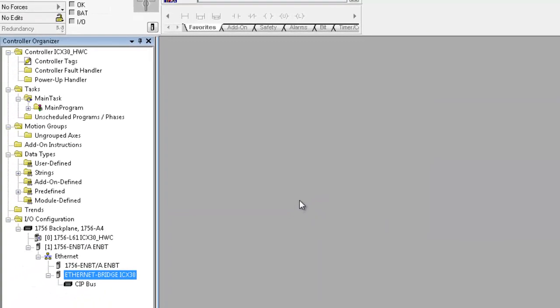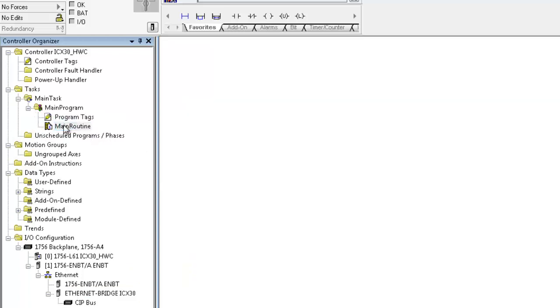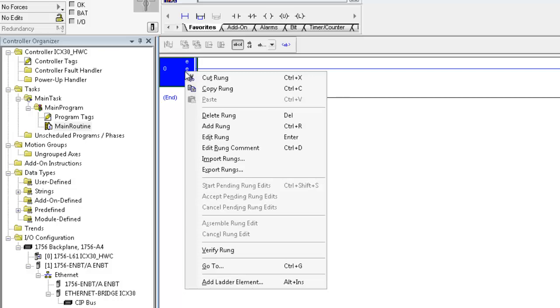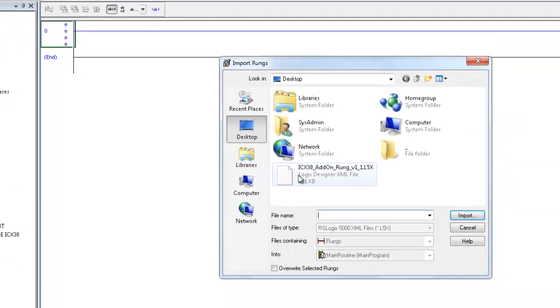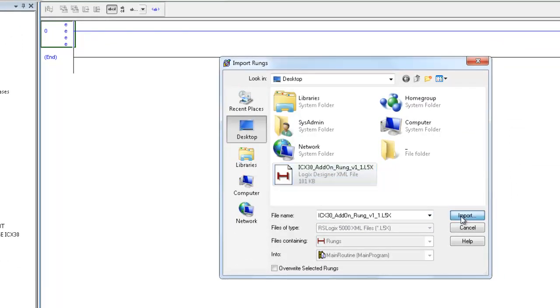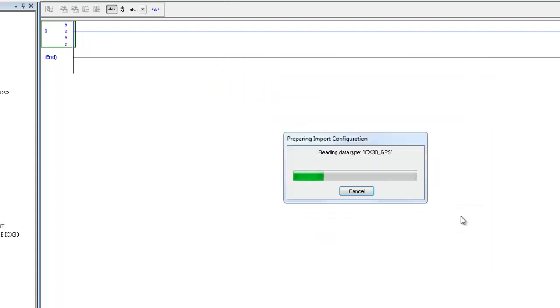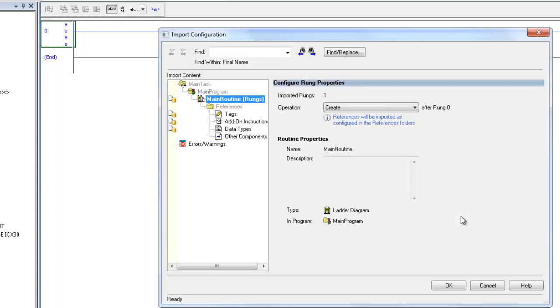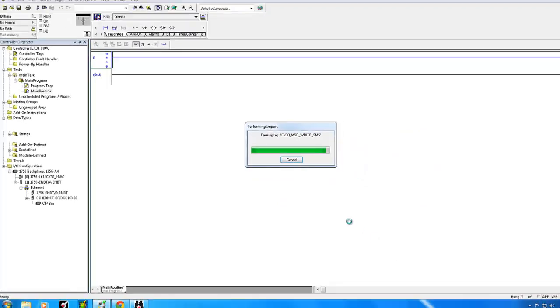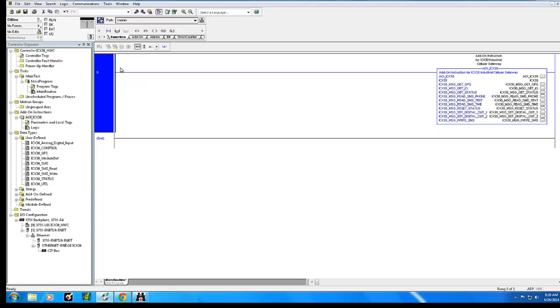Now we can import the add-on instruction to our project. Right-click on any available rung and choose Import Rung. Navigate to the ICX30HWC add-on rung. Select the AOI and click Import. The add-on instruction can be found on our product DVD that ships with the module or on our website. When the Import dialog box opens, click OK and the import process will begin. Once the import is completed, open the controller tags.